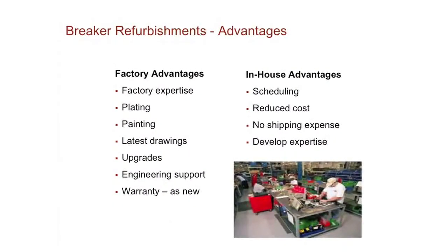When we look at the breaker refurbishment advantages, on the factory side, we obviously have the factory expertise. When we look at the ITE lineage breakers, we actually have a shop that tears them down completely to every nut and bolt, as you can see in that picture there. We clean them, re-grease them, repaint them, replate them, everything. This facility is actually capable of doing 1E or nuclear type work, so that's the level of competence we have at that facility. If you run it through the factory, we obviously have the latest drawings, so any upgrades will be incorporated. The warranty we give is as a new breaker: 12 months from the time of install or 18 months from the time of delivery. So basically you've got a pretty good situation here on the factory refurbishment.